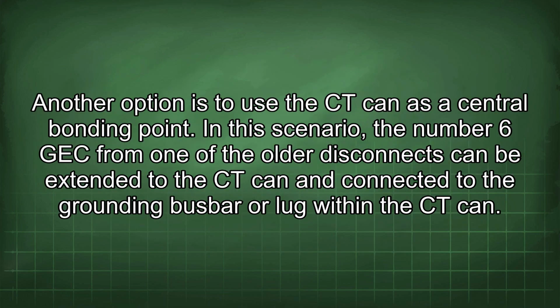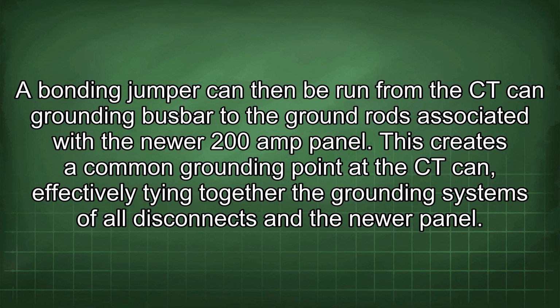Another option is to use the CT can as a central bonding point. In this scenario, the number 6 GEC from one of the older disconnects can be extended to the CT can and connected to the grounding busbar or lug within the CT can. A bonding jumper can then be run from the CT can grounding busbar to the ground rods associated with the newer 200 amp panel. This creates a common grounding point at the CT can, effectively tying together the grounding systems of all disconnects and the newer panel.